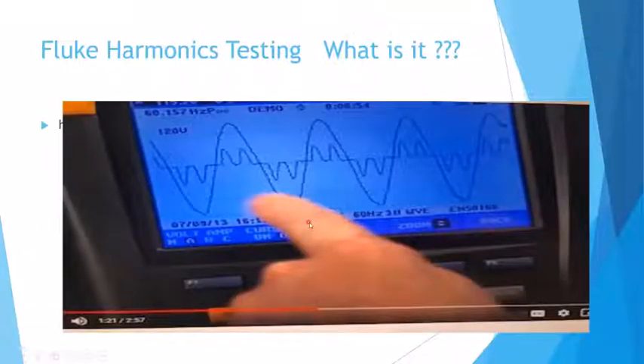So the reason I talk about that is I've used that meter now for well over 20 years. It's advanced quite dramatically from when I first started playing with it. But again, this shows that voltage waveform, and from those probes it also shows the current waveform. So you actually see what's really feeding out to the motor, because a lot of people are used to just putting on a clamp-on ammeter, and it's just digitally telling me these values, but it's giving you what they call the RMS value. So it's not what the actual spikes are, it's what it's calculating. So you may see it's showing 20 amps, but you may not see that there's maybe a large jag or spike in there. And that's what motors don't like. Windings of motors are very critical.